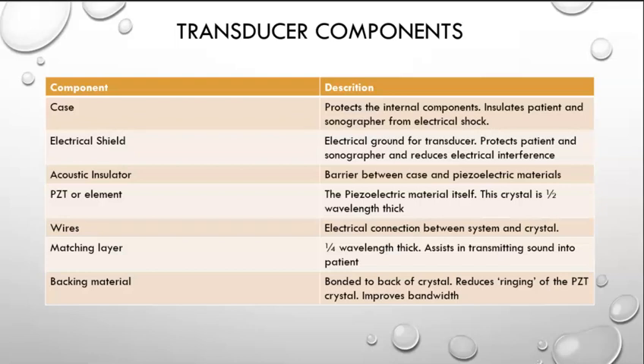There is an electrical shield within the transducer. This is what's known as an electrical ground, and it protects the patient and sonographer, and it helps reduce some of the electrical interference that can occur in a hospital setting. There is an acoustic insulator that provides a barrier between the case and the piezoelectric materials. These piezoelectrics are very sensitive to sound, as you can imagine, and so we have to have an acoustic insulator to keep outside sounds from causing the material to vibrate.